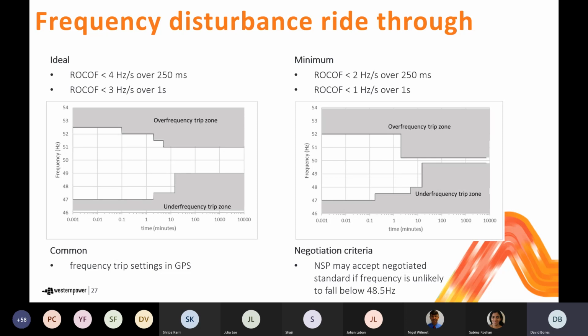So jumping back to the frequency ride-through requirement, it's illustrated on this slide. You can see the ideal standard illustrated by the diagram on the left and the minimum standard illustrated by the diagram on the right. The way to interpret these standards is you need to remain in operation, providing the frequency remains within the white area shown on these diagrams. If the frequency was to deviate into the grey area, then that's permissible, the generator may disconnect under those conditions. And you can see there's some quite wide frequency deviations characterised there by the ideal and a slightly narrower set of frequency deviations for the minimum.